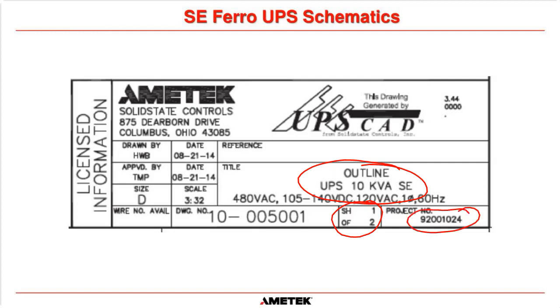If you ever contact the after-sales service department here at AMETEK Solidstate Controls, we are always going to ask you for the serial number. And the serial number is also called the project number on the drawings. And that is how we reference everything in our computer system. If we're looking for the drawings internally, or if we're creating a work order, or if we're doing anything regarding a UPS, we need to have the serial number, because it will tell us exactly what system we're dealing with, what the options are. It gives us all the information that we need. So that is the important thing about that bottom right-hand corner.